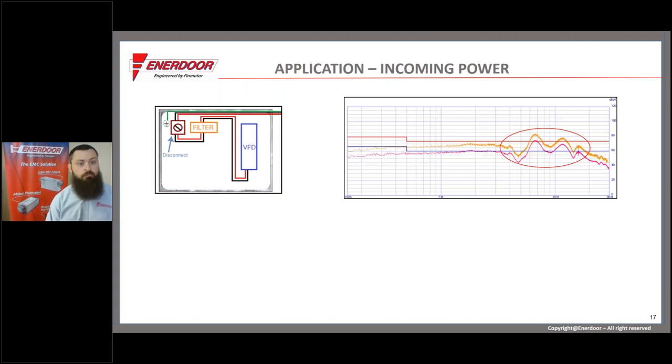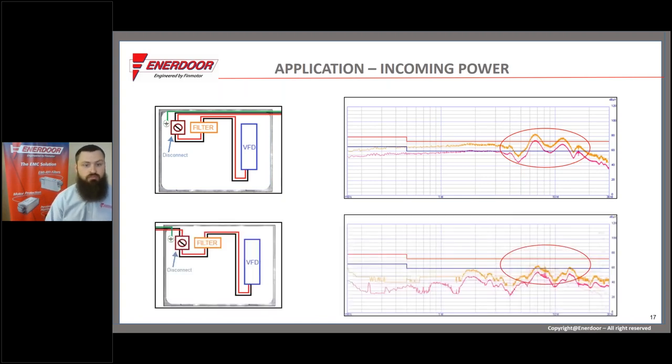The engineer talked to the on-site electrician and asked if they could reroute power to come into the left-hand side of the enclosure. The electrician said it wouldn't be a problem. They did it in a few minutes and retook the scan. This simple change — no new filter, no different VFD, just a different power entry point — had a really significant effect on the scan results. That's what Enerdoor likes to do: find simple solutions that help manufacturers meet compliance with as little pain as possible.